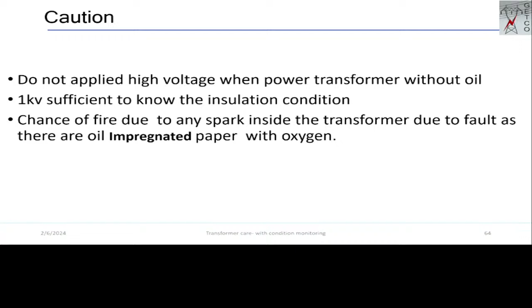Here I just want to give a highlight: without oil, please do not test the transformer at higher voltage. Okay, otherwise there is a chance of fire. Please do not test winding resistance at higher ampere also. So this transformer result was found normal and we put it back into service, and after filtering we tested all the 10 kV. Okay, so 1.40 crore saved in this transformer.